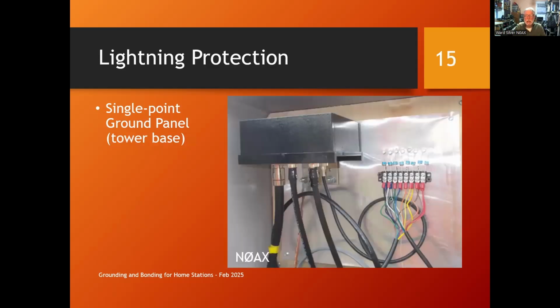Here's an example at my station. I have three 60-foot towers running along a high spot between a couple of ravines. And I know these things get hit by lightning. I've seen burned trees and all this kind of stuff. So at the base of each tower, in a surplus electrical fiberglass box, I've established a single point ground panel at the tower base. And you can see an RCS4 remote coax switch here. This is an L version, which means it has a gas discharge tube on each one of these antenna lines and the incoming hard line here.